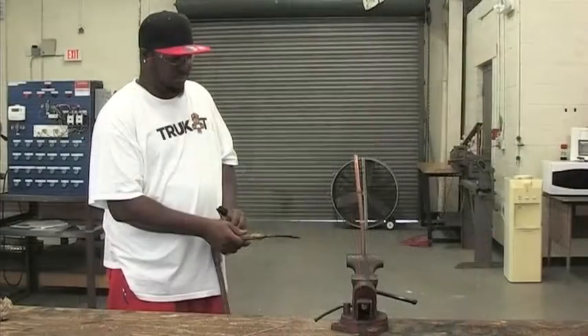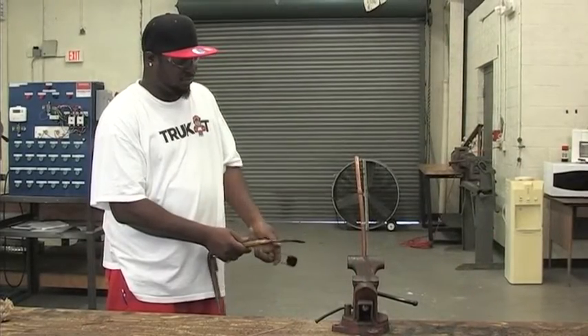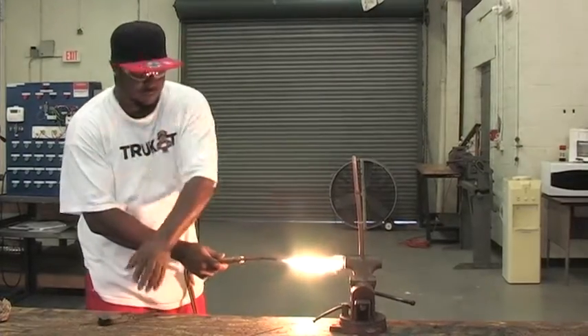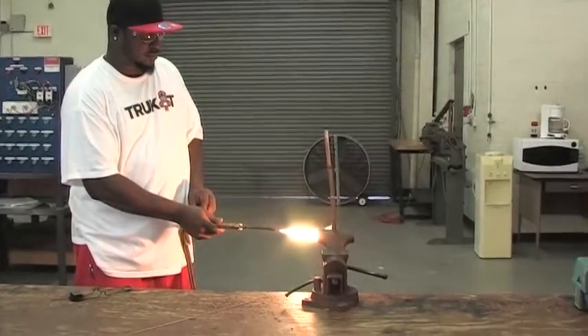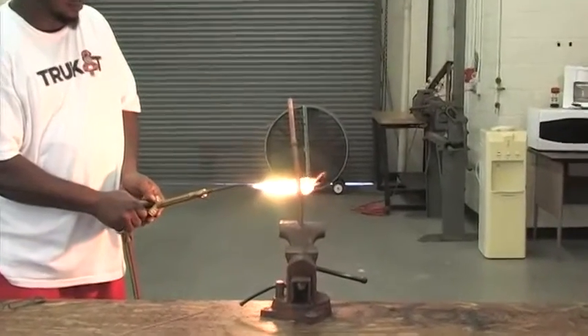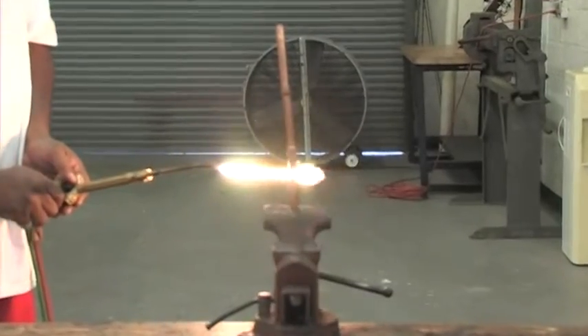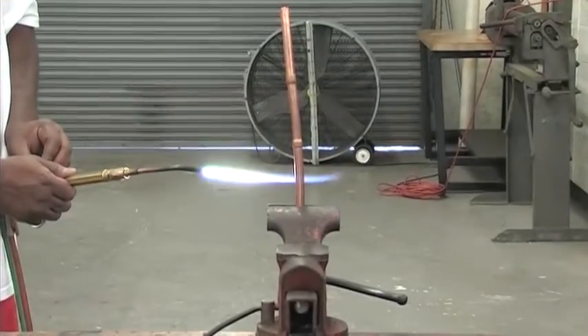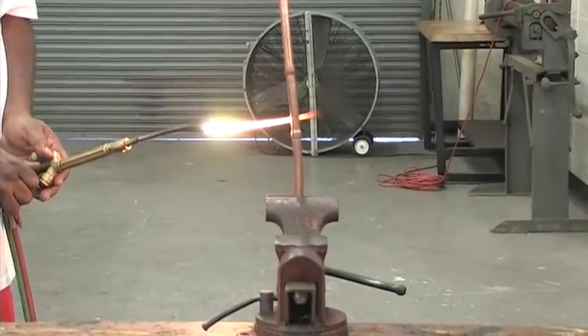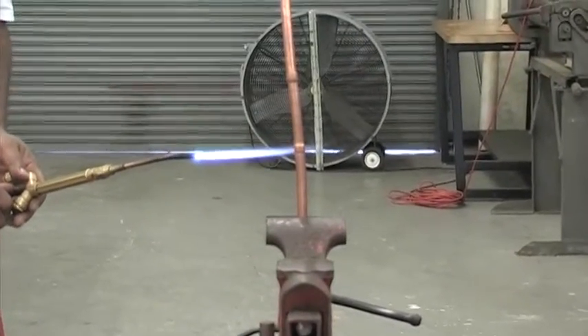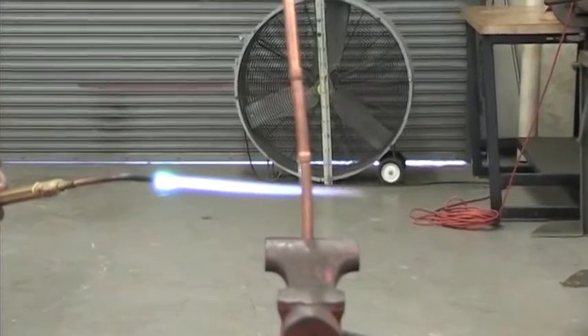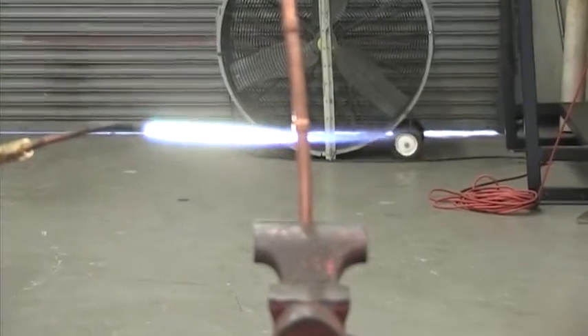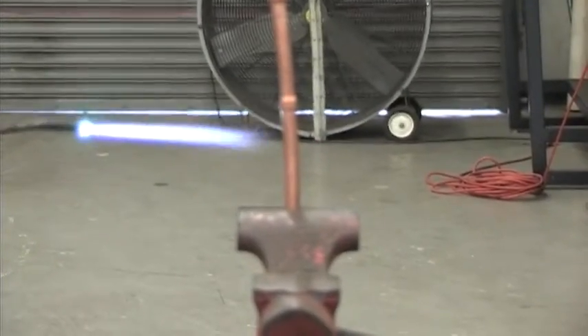I'm with Toy Reed here. Toy is going to show you how to solder and braze copper piping that we use in the HVAC field. Toy is fixing to light the torch. This is an oxyacetylene combination used to braze refrigeration piping. He is now adjusting the flame for the proper heat to braze with. You always want to have a flame that has some noise to it. That way you know you have the correct amount of heat. You look for a good blue neutral flame.